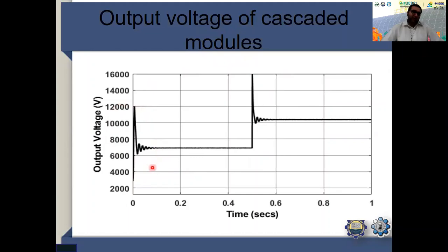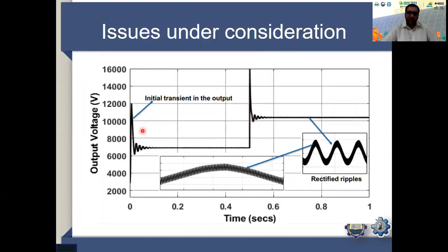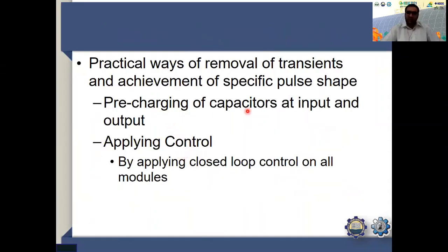But here we have this type of transient response that is clearly not acceptable for the magnetron, being a very sensitive load. Therefore, there was a need to remove such transient behavior from our output. Otherwise, our magnetron will be damaged immediately. On investigation, we came to know that this was due to some surge current drawn by the filters at the input side. There could be 2 methods to eliminate that. One, the pre-charging of the capacitors at the input and output, and secondly, by applying control.